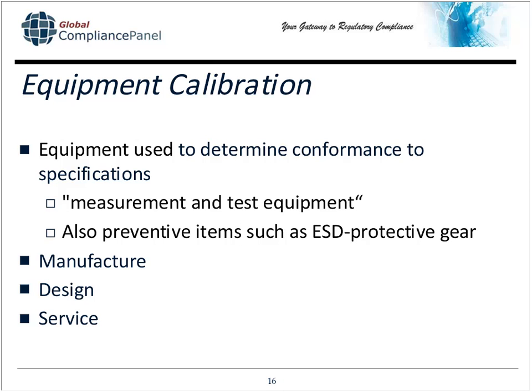So you've got to make sure that all measurement and test equipment, independent of what department uses it, undergoes calibration. Also, things like ESD protective gear, whether it's the wrist straps or the placemats, those have to be in your calibration program as well. Anything that's used in manufacture, design, I mentioned already, anything that your servicing department uses has got to be under equipment calibration.